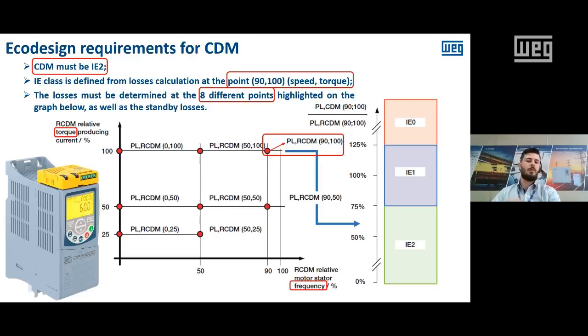So you might be asking, why do I need to define losses at 8 points if I just define the IE class with the 90-100 point? The reason is simple. A variable speed drive is usually applied in applications where the load varies, and thus the speed of the motor is going to vary, or the torque of the motor is going to vary. And in these applications, the point of operation may not be the 90-100, but it could be something different, such as 50% speed and 75% of torque. So using all these 8 points and using the methodology explained in the standards, you can define the losses at any point of the variable speed drive. So you can define the losses at the exact point where you are going to operate this product.